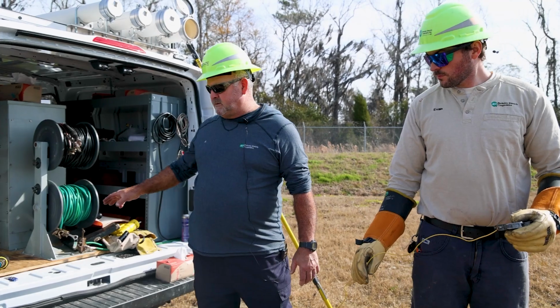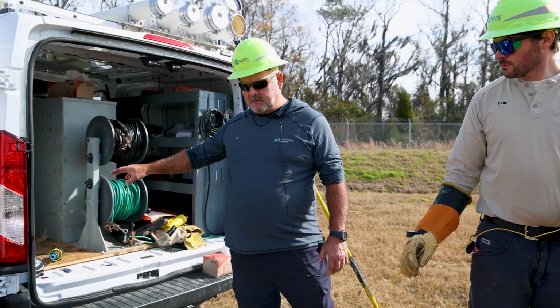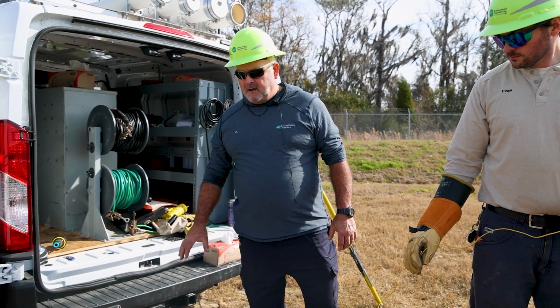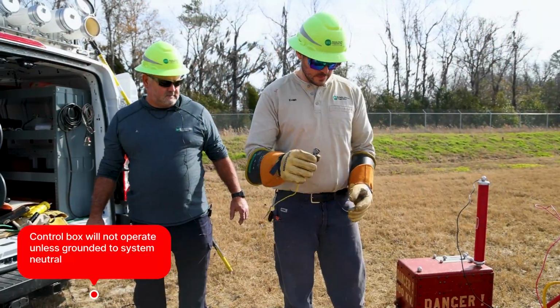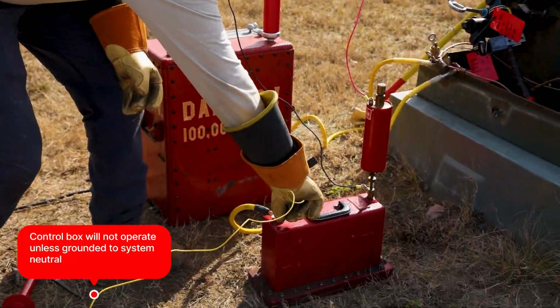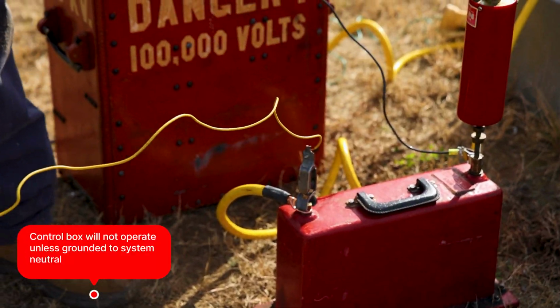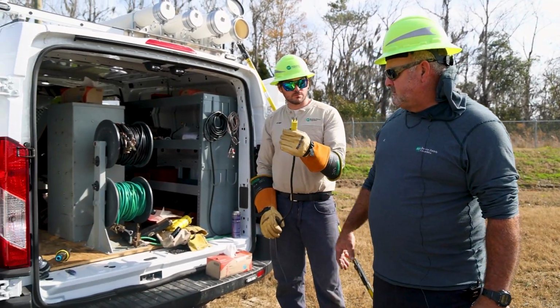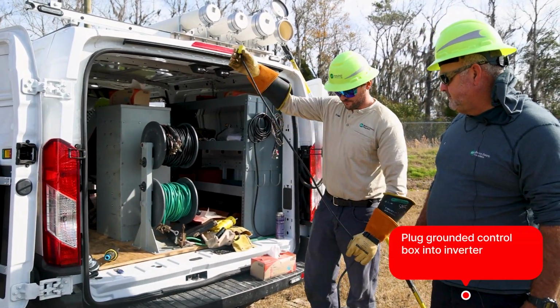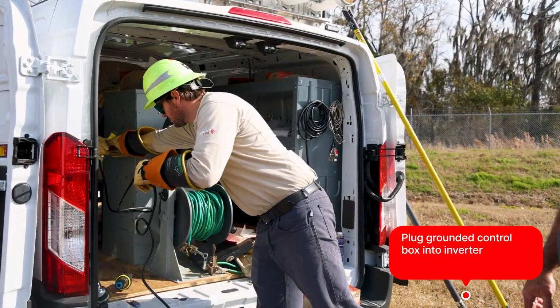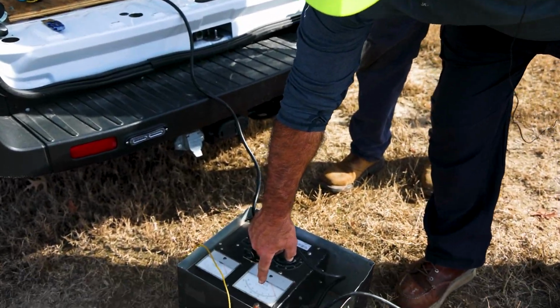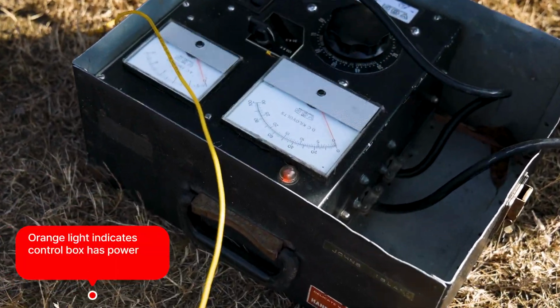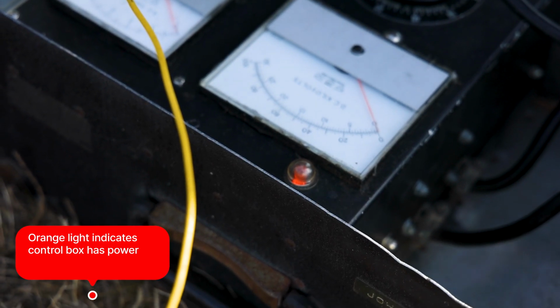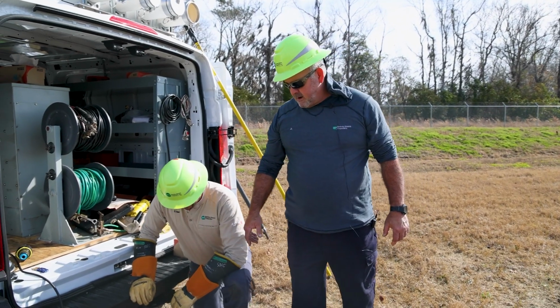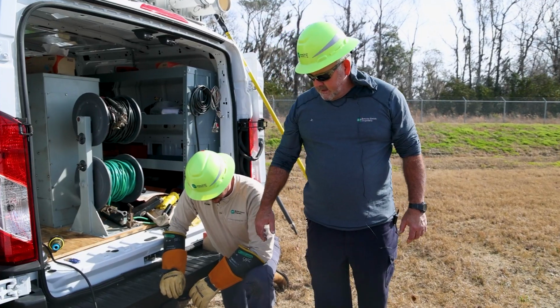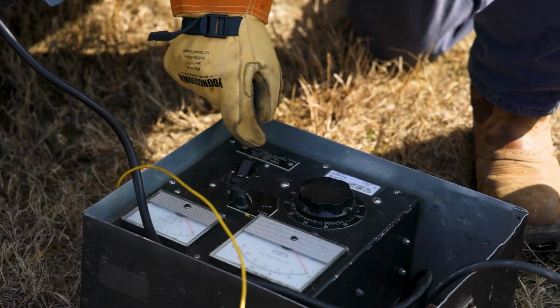Now, being that we are using an inverter for power to supply the control box, the control box will not come on unless it is grounded back to your system neutral. After your ground is hooked up, you can plug your control box into your inverter for power. There's a little indicator light on the top of the control. When it lights up orange, that means you have power to the control box.